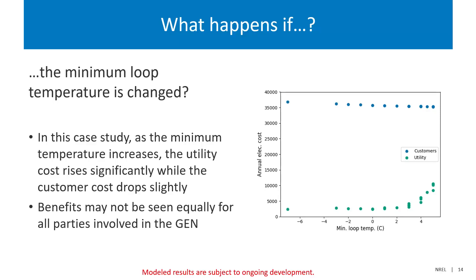We build out all this modeling to answer interesting questions. The first example: what if you changed the minimum loop temperature? The way our control system is set up, you decide when pumps ramp up, when the borehole gets used, and when auxiliary heat turns on to maintain a minimum temperature. We found that as you increase that minimum loop temperature, the cost to the utility goes up greatly — they're working hard to maintain higher temperature — but the cost to the consumer goes down slightly because their heat pump is working more efficiently. You see this trade-off in annual electricity costs, highlighting how benefits must be shared among all parties.